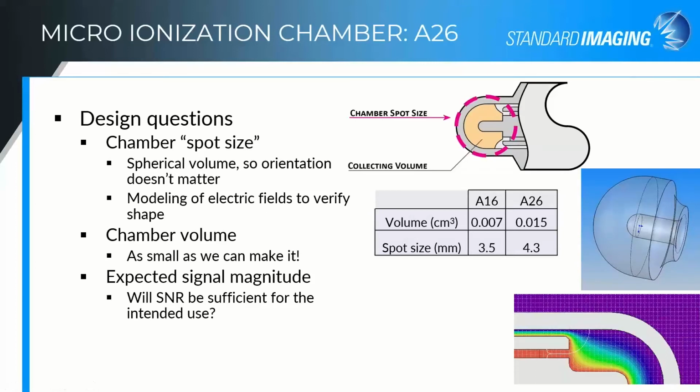The rule of thumb is usually that your field needs to be, now I'm going to quote it wrong, I think 2.5 times the width of your ion chamber. That's what the AAPM recommends. I think IAEA as well, although that's a good question. So it really depends on the size of, or the profiles that you're looking at, and just how much perturbation you are introducing that you're comfortable correcting for in those small fields.